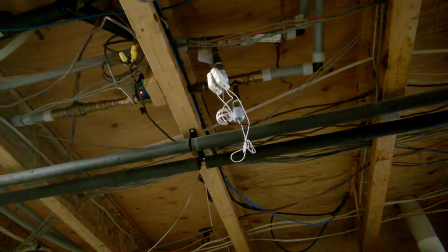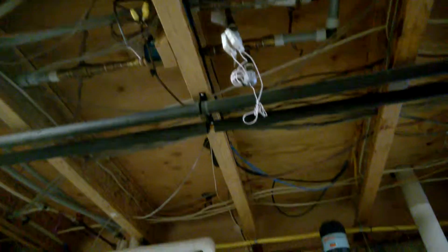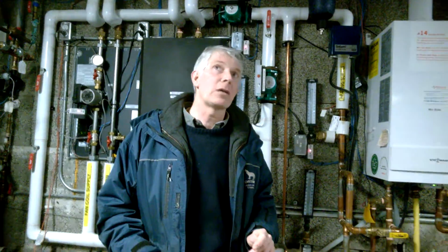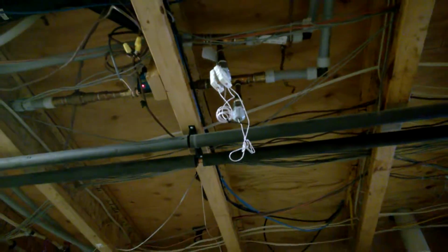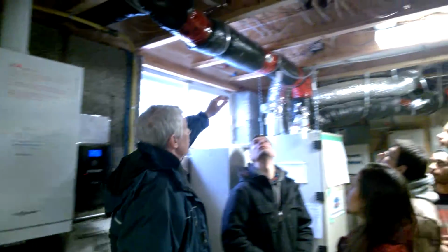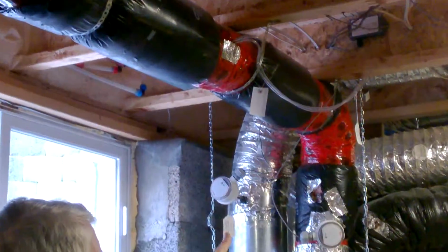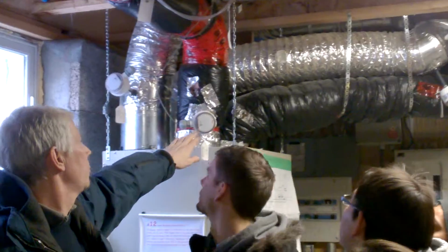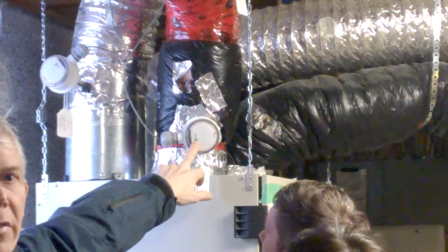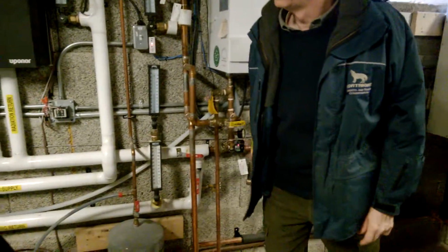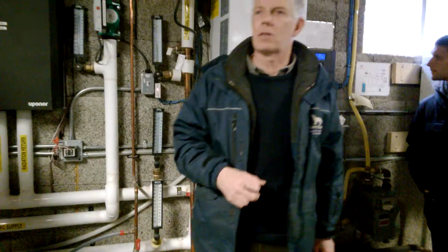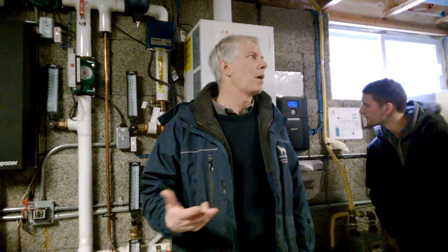What are these? They're everywhere. Yeah, those are all our instruments. So there's 300 data acquisition points in the house, and that's how we measure the performance of everything. So these are the temperature of the fluid going to and from that coil. These are airflow sensors here, so the amount of air that's going through the heat recovery ventilator. I'm also measuring, you can see the little blue dot on there, the relative humidity and temperature. This is a flow meter here. So everything that moves in this house that has anything to do with energy is measured.